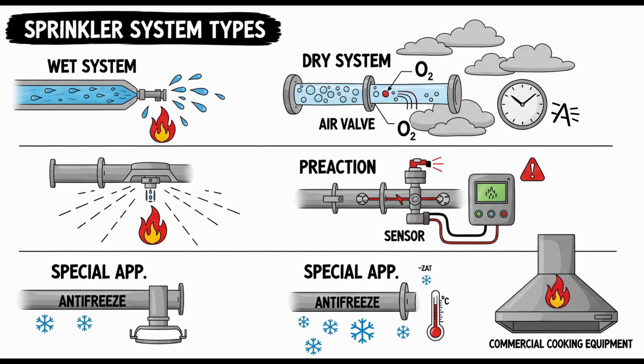Okay. And sprinkler types allowed on pre-action systems? The permitted sprinkler types and arrangements are the same as specified for dry pipe systems. Upright, listed dry sprinklers, and pendant sidewall sprinklers only when installed on return bends in heated areas or using listed piping, copper, CPVC, with potable water in areas kept above 40 degrees Fahrenheit. So the same rules about preventing water trapping in cold areas apply if those sprinklers are on a pre-action system, even if the main system is protecting a sensitive area. Exactly. The physics of freezing don't change. And one more configuration point. Double interlock systems, and any pre-action systems protecting storage occupancies, except miscellaneous storage, are explicitly not permitted to be gridded. Same prohibition as dry pipe systems. Keep it simple, no grids for these either.